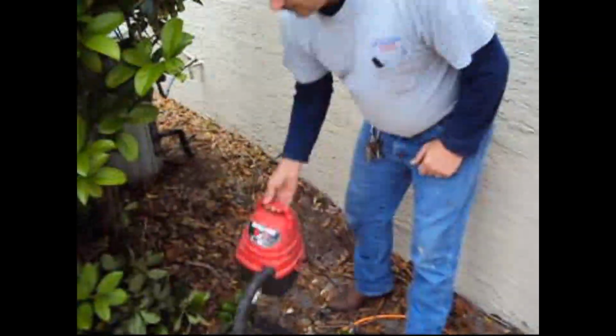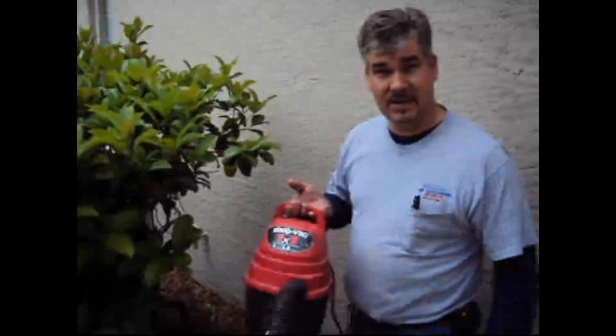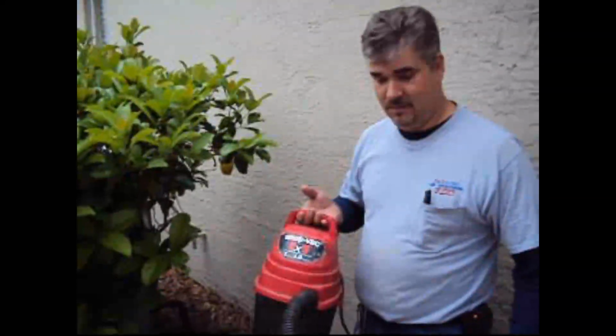So the first thing that you need to do is make certain your vacuum is a wet or dry pickup vacuum cleaner. Run an extension cord to the outdoor unit. If you look at the outdoor unit, you'll see some piping coming in from under the house. This is refrigerant piping, and this black flexible pipe that's sticking up right here is your drain line.